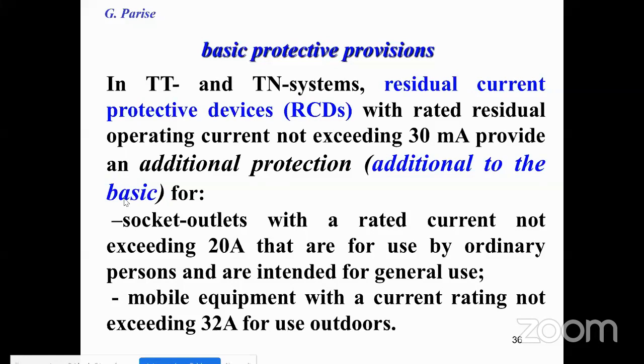The requirement to adopt, in a mandatory way, a residual current protective device with a value of 30 milliamps is only for additional protection. And this adoption is mandatory for socket outlets with a rated current not exceeding 20 amps that are for use by ordinary persons and are intended for general use. It's mandatory also for mobile equipment with a current rating not exceeding 32 amps for use outdoors.